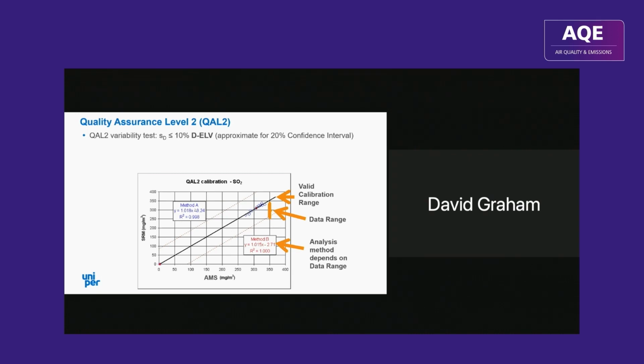The only test is a variability test. So this is looking at the data scatter, and it's the standard deviation of differences between the test measurements and the calibration line. And broadly speaking, for a confidence interval of 20%, that has to be less than about 10% of the daily ELV. However, the test laboratory comes back a year later, performs the AST, and then they must check that the absolute average difference between the new test points and the original calibration line is better than a tolerance, and that again is 10% of the daily ELV.